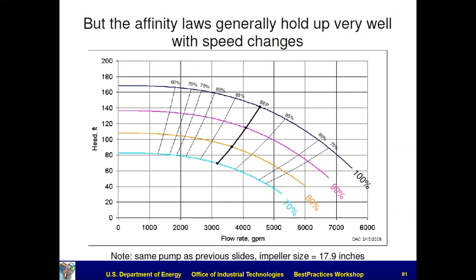So you get that point. And then if you want to run your 90%, you take each one of those points. Say I take this point, and okay, if I reduce the flow by, let me see, what do I do? If I go to 90% speed, I go to 90% flow. So I cut the flow in linear relationship with the speed reduction that I want.